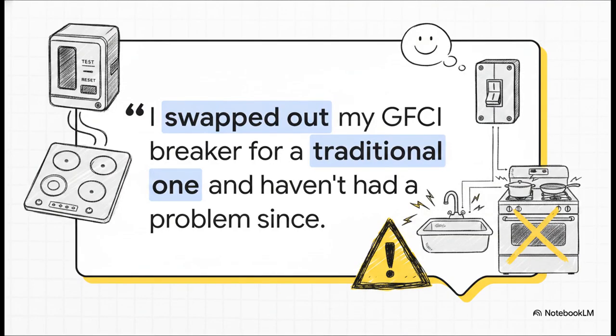Which leads us to an incredibly satisfying but honestly kind of frustrating solution. Our Reddit user basically just ripped out their code-mandated GFCI breaker and completely replaced it with a traditional older-style breaker. And guess what? The false tripping stopped instantly. The stove works perfectly now. But think about that for a second. Technically, because that outlet was near a sink, they had to bypass the exact safety code meant to protect them just to be able to make dinner.